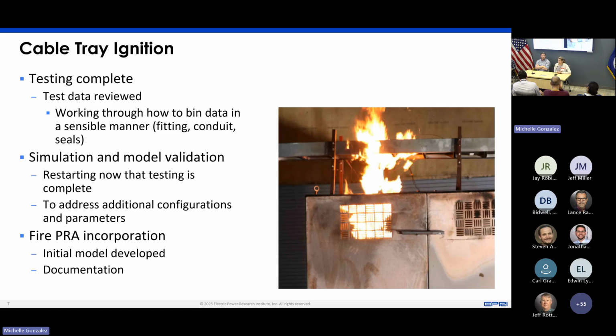Now that testing is complete, we're looking at additional simulations to provide data points for configurations that couldn't be tested. Hopefully that's complete this year, and next year we could spend effort on model development and how that could be implemented into fire PRA results. The intention is that this would provide an alternative way to calculate time to damage for the cable tray, which, if the results pan out as they looked in testing, would provide additional minutes to credit before cable tray time to damage, resulting in lower non-suppression probabilities.